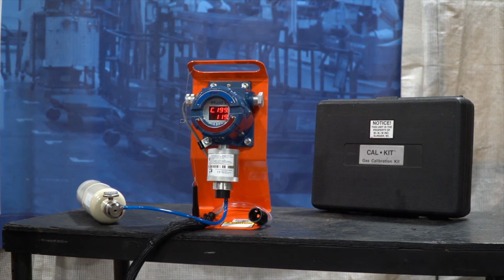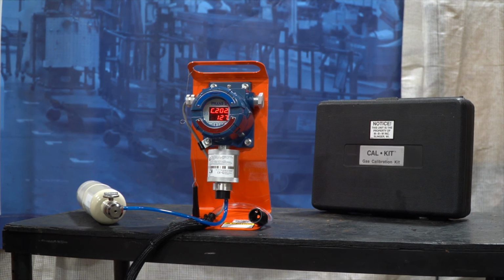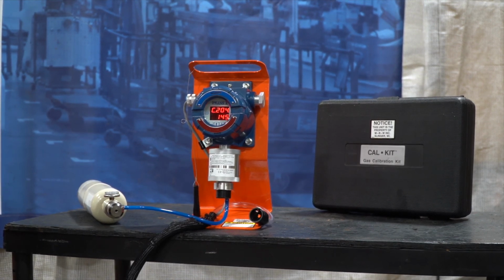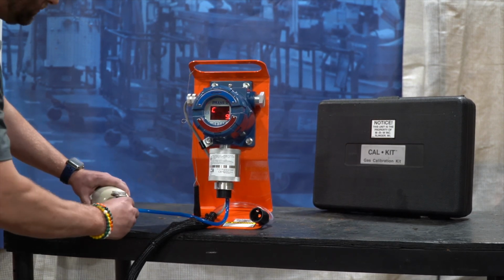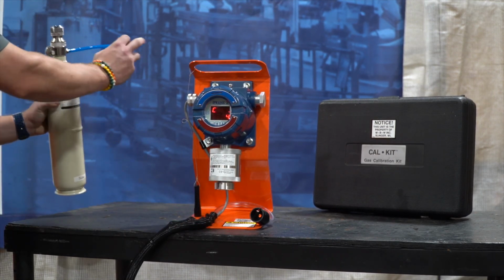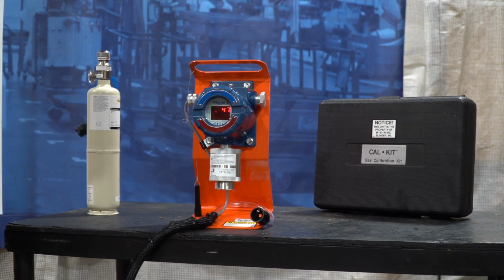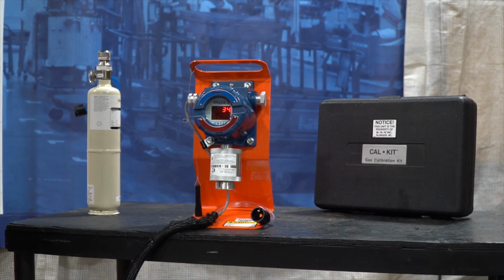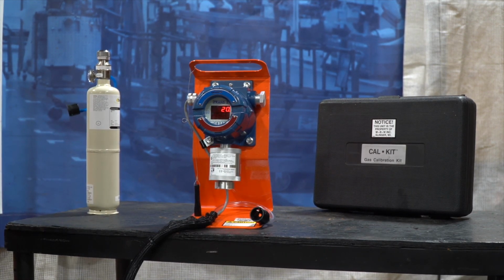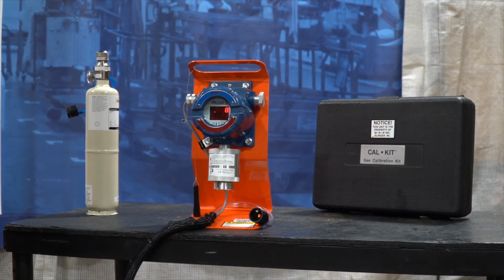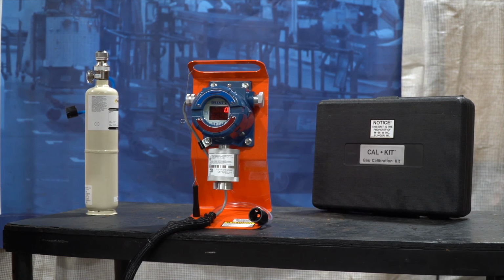So now we're just going to wait for the number on the bottom right to stop counting up and start counting down. And that is when we decide to disconnect the calibration gas. Now I've removed the cup and turned off the gas. And if done properly, the sensor will read a 0 when completed. And the sensor reads 0, you have completed the calibration process.